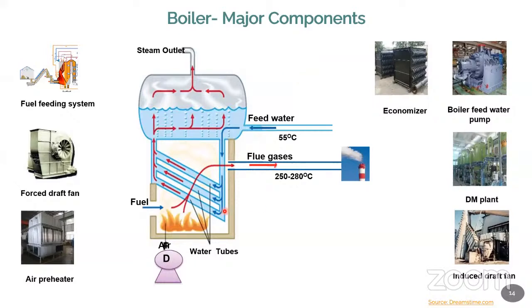Please continue. So when you pump more air, then automatically the heat generated by the fuel or by the system will be completely taken by the flue gas. So you must be very careful by monitoring the temperature. When the temperature is very, very high, that means your flue gas will take more heat. That is completely wasted. You are burning the fuel to take the energy for heating the water, but the energy is going into the flue gas, and through the flue gas you are wasting the energy. Okay, so you need to monitor the flue gas temperature.